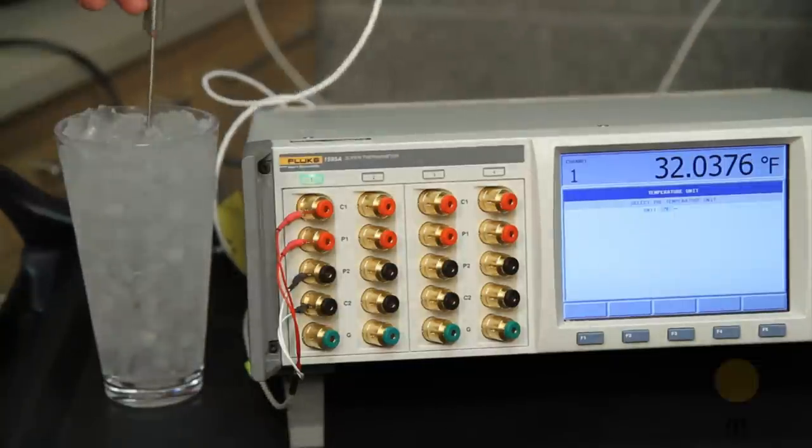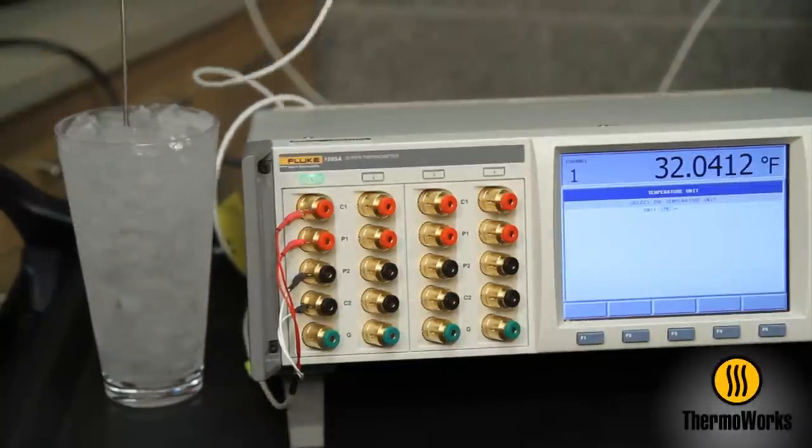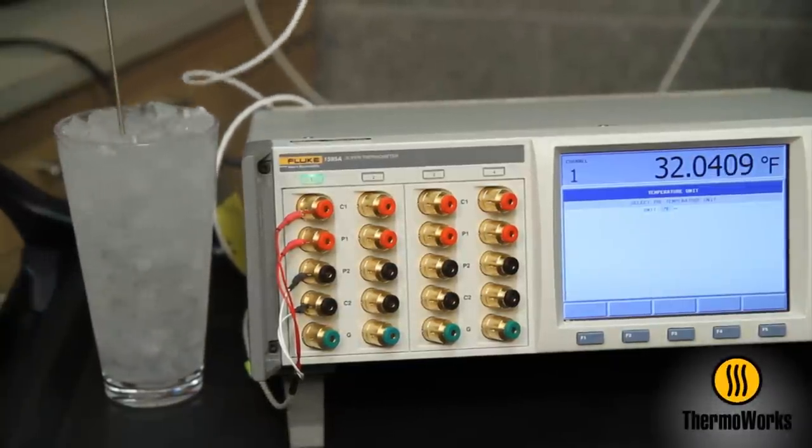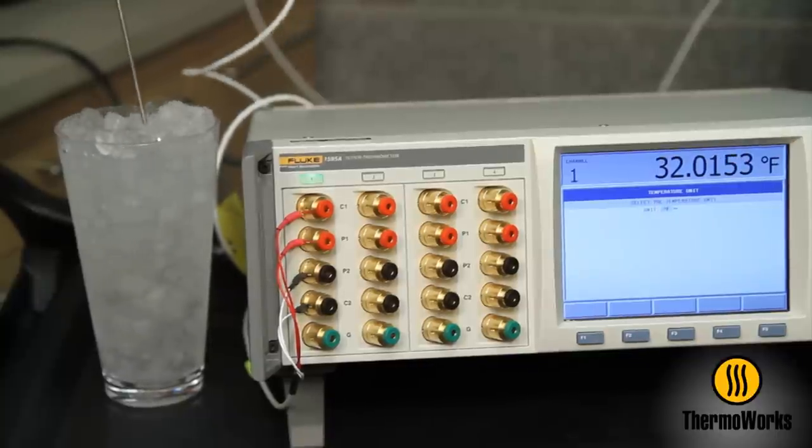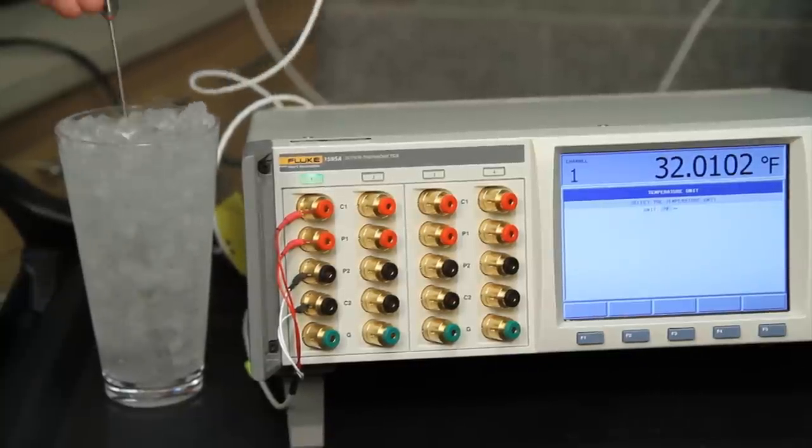Placing the probe in the center of the ice slurry keeps us away from the warmer bottom and sides of the glass, and stirring the probe keeps the sensor from resting against an ice cube, which will affect your reading with these faster, more accurate digitals.